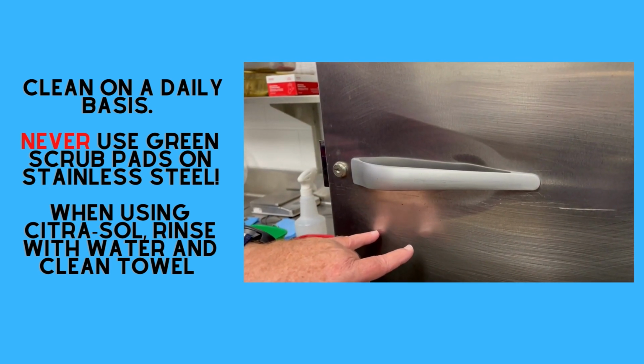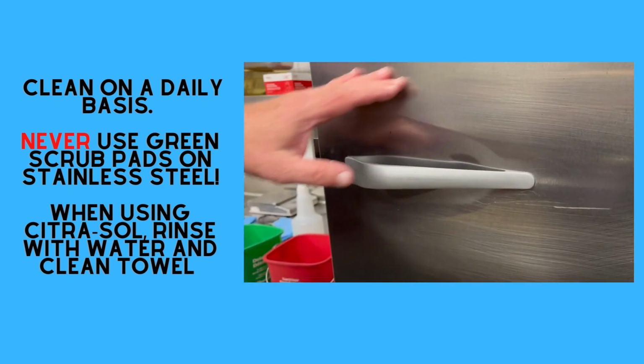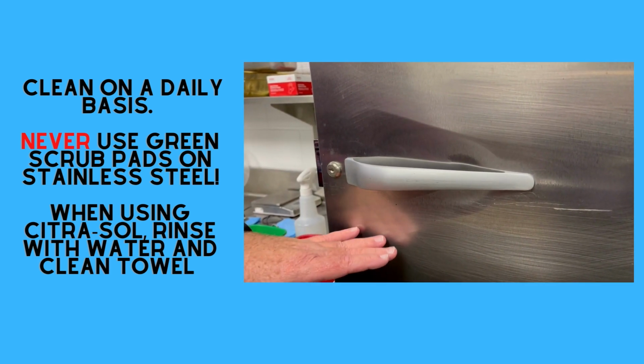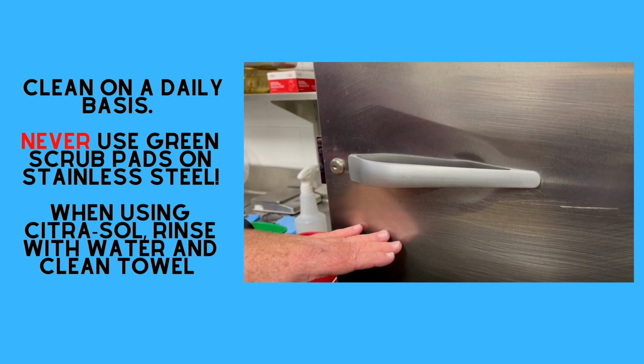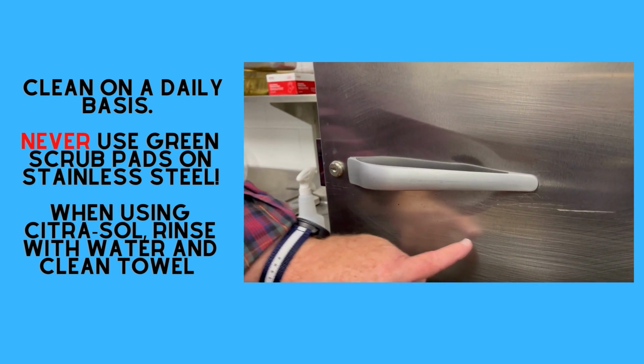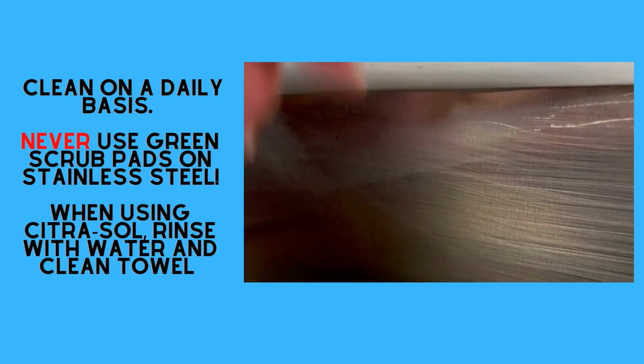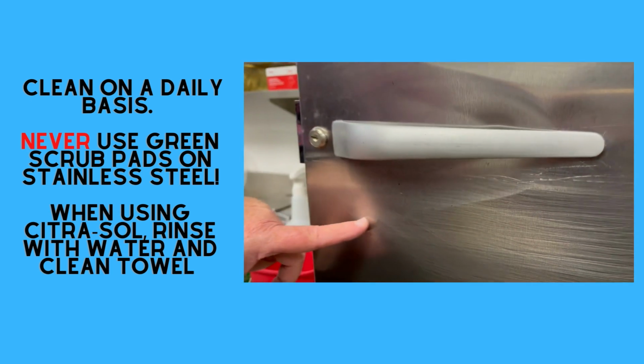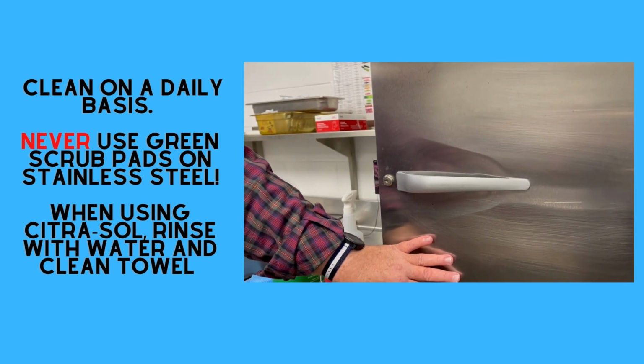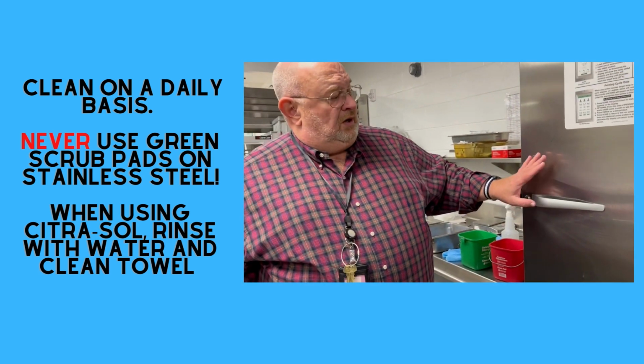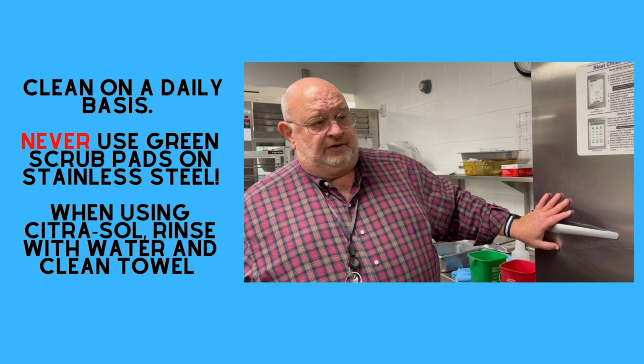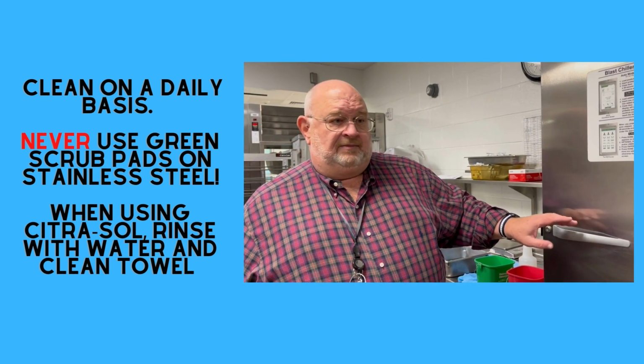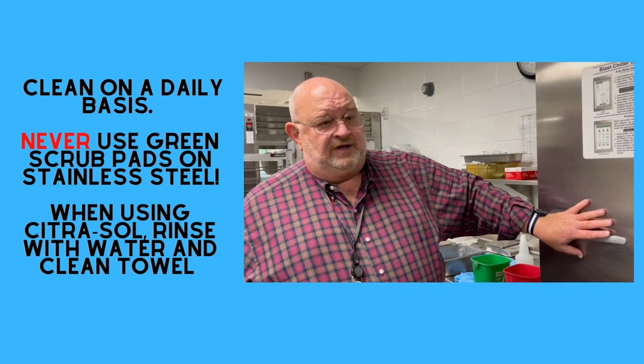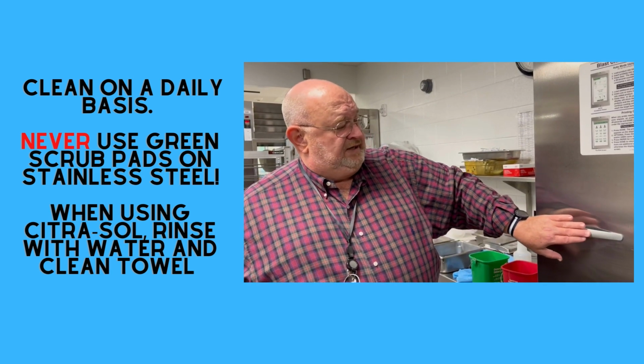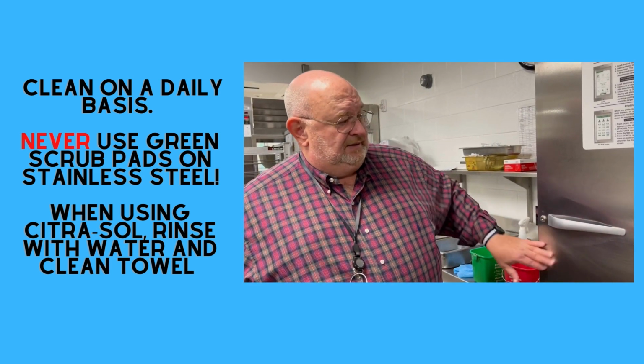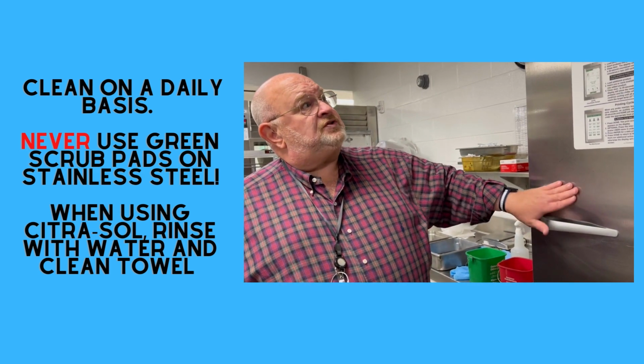But if you have heavy residue on stainless steel, you may think you want to use a green scrubby pad. If you'll zoom in and you see these scratches, that's what happens when you use a green scrubby pad on stainless steel. Okay? All you really need to do is Citra-Sol cleaner, rinse it, and make sure it's nice and clean after every day. And you won't get any buildup that needs to have a scrubbing that could just color the stainless steel.